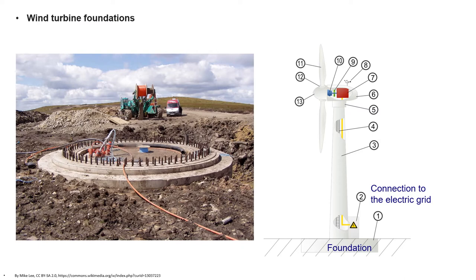The generator in a wind turbine produces alternating current electricity. Some turbines drive an AC/DC converter which converts the alternating current to direct current with a rectifier and then back to alternating current using an inverter, in order to match the frequency and phase of the grid. However, the most common method in large modern turbines is to use a doubly-fed induction generator generally connected to the electricity grid.